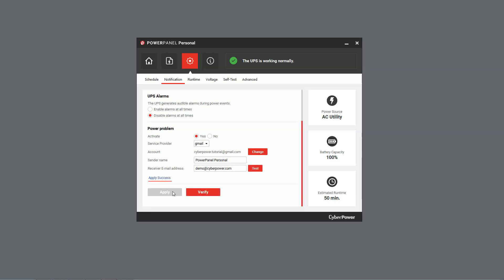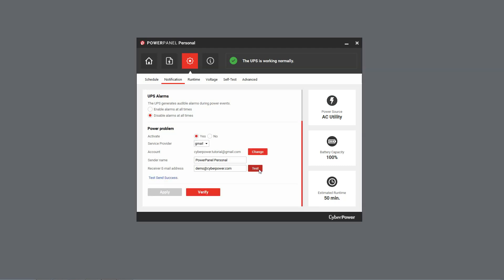Then click Apply. Once the setting is applied, click Verify to validate the email sender setting. When the successful message shows up, click Test as the final step. An email with the subject power event notification will be sent to the recipient to make sure the notification system works properly.